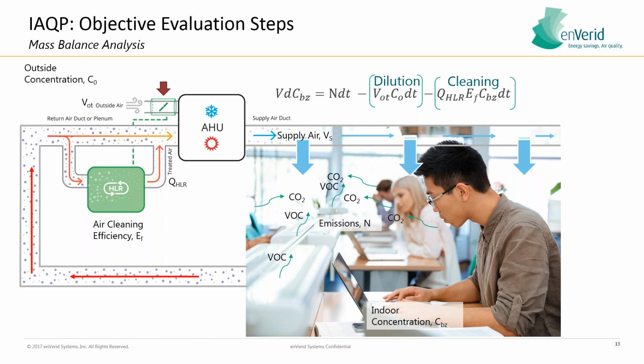The only thing the indoor air quality procedure does with this mass balance equation is give you another lever to pull, which is air cleaning. So you have one more thing in addition to bringing in outside air for the purposes of pressurizing the building. You can use air cleaning to help remove some of those emissions as well.